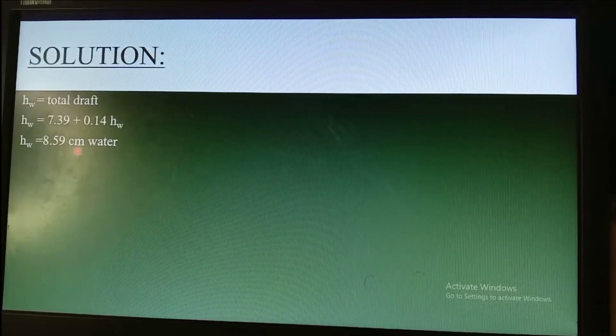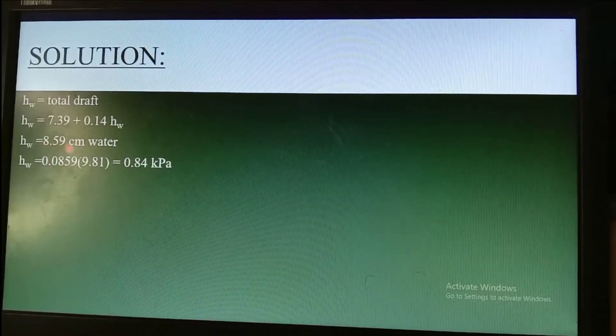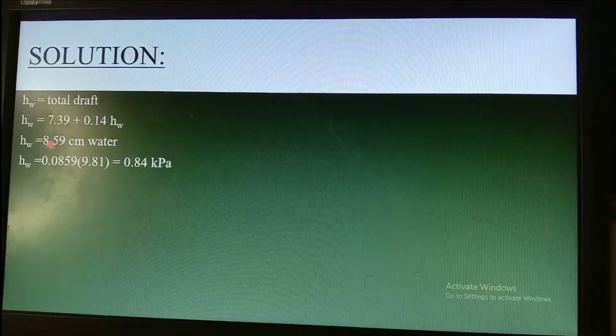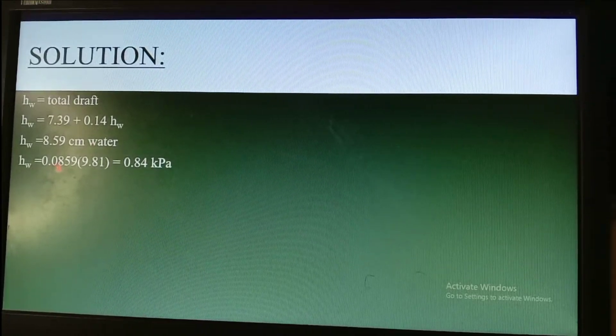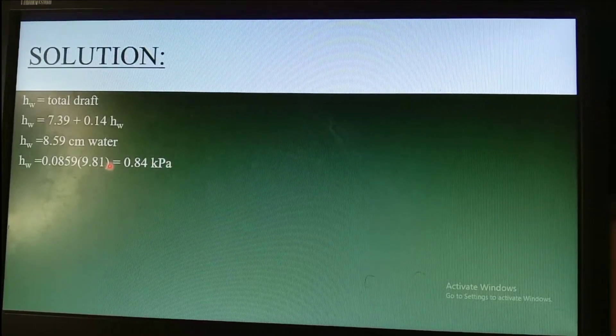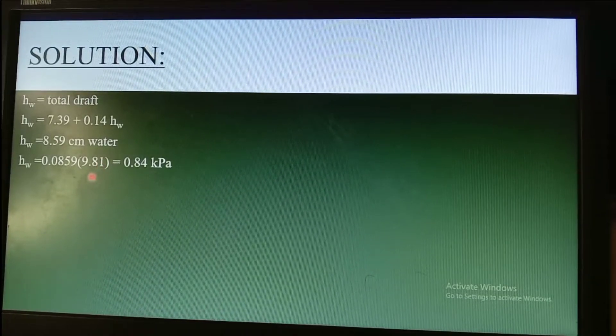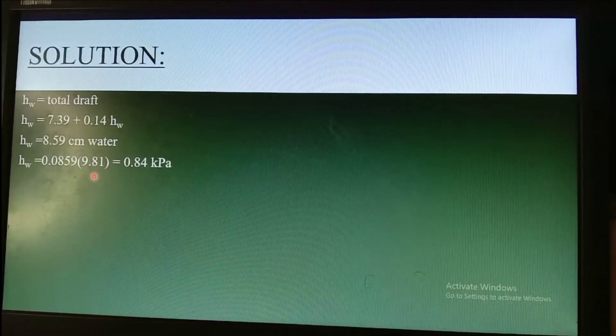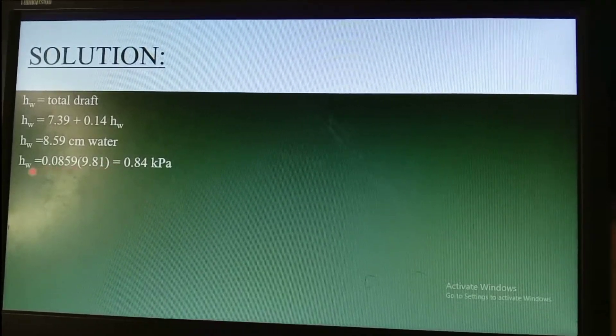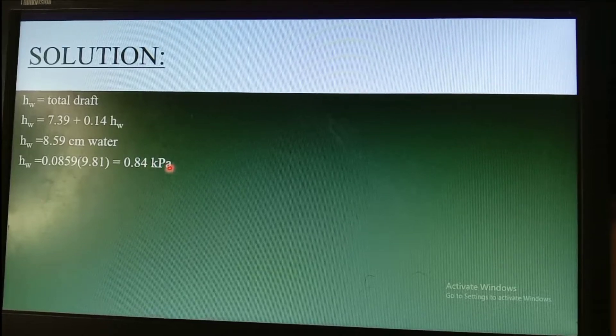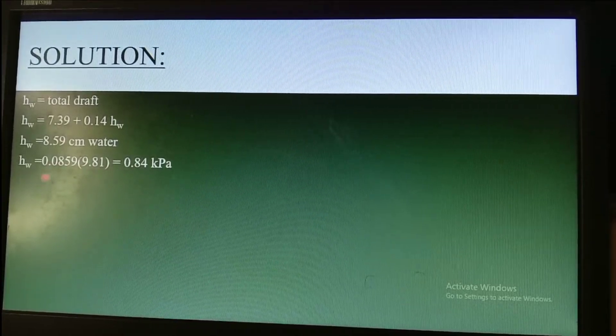We convert 8.59 centimeters of water into kilopascals: divide by 100 to get meters, then multiply by 9.81 kN/m³. The resulting total draft pressure equals 0.84 kilopascals (kilonewtons per square meter). This is the calculated total draft pressure of the chimney.